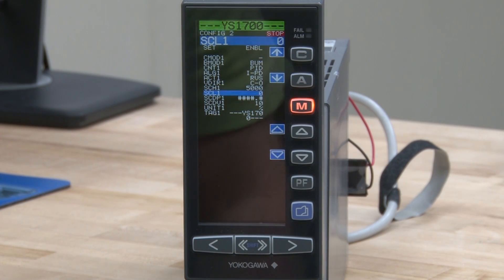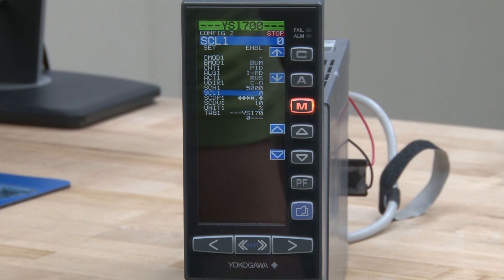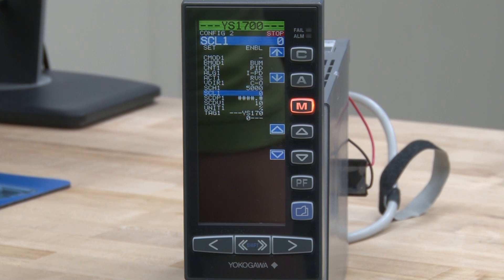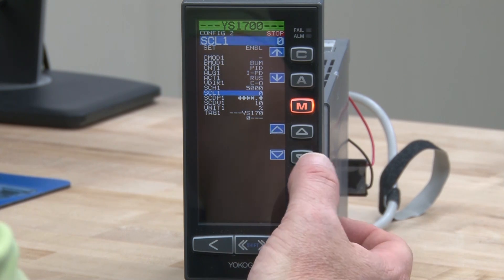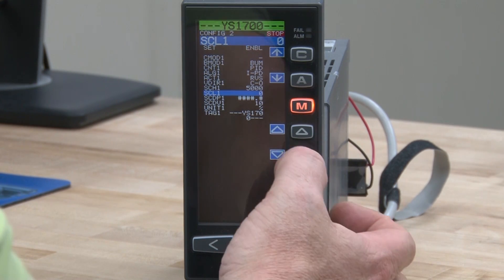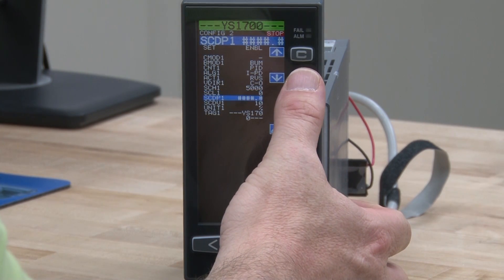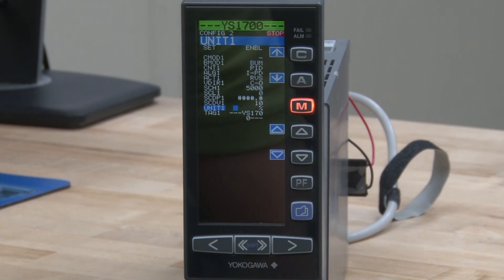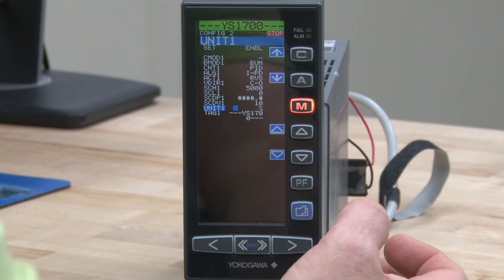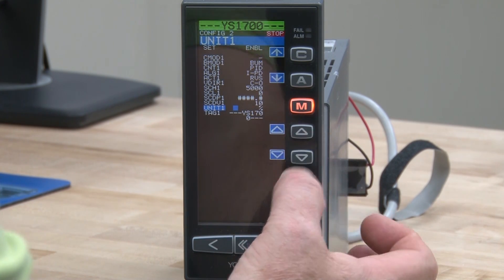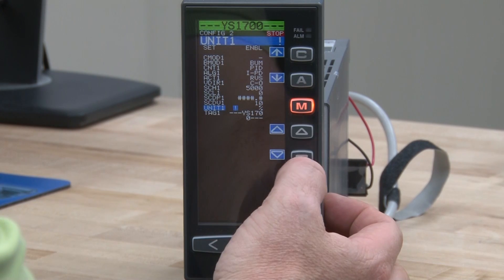The scale low, as we already discussed, is going to be zero for our 4 milliamp or 1 volt signal, so we can leave that the way it is. We've finished the scaling portion. Now we can move down to the unit, which is just a tag for the engineering units. We're going to change it from percentage to GPM.